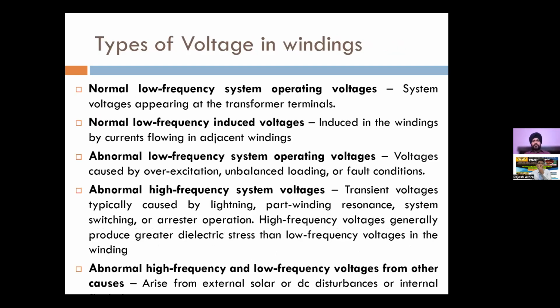Then if we talk about the types of voltages which are seen in the windings, the first is the low frequency or 50 hertz system operating voltages, which is the induced voltages on the transformer terminals. Then these induced voltages can also cause flow of current in the adjacent winding, and this is also of the same 50 hertz frequency. So this is the induced voltages in the adjacent winding. Then there can be abnormal low frequency system operating voltages. This can be due to overexcitation or any unbalance in loading, which can cause a low frequency flow of voltages.